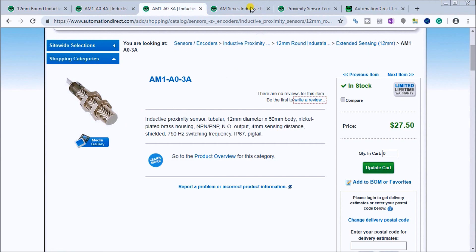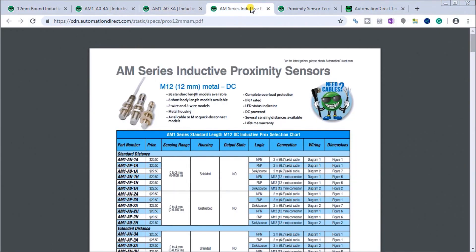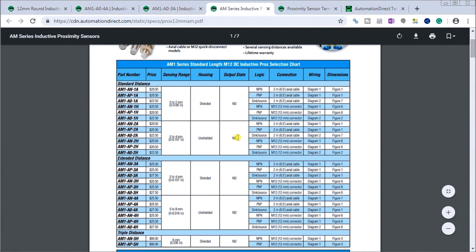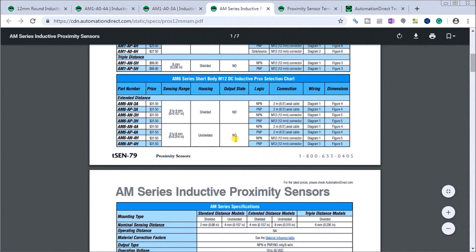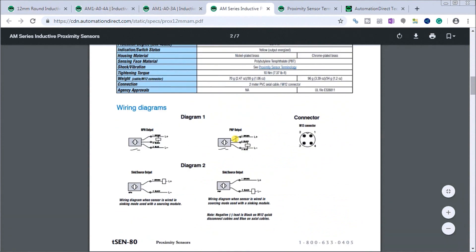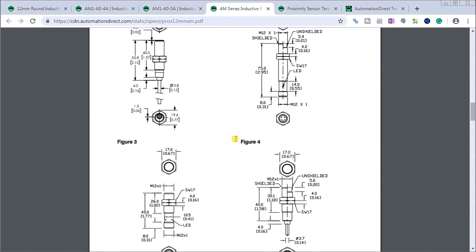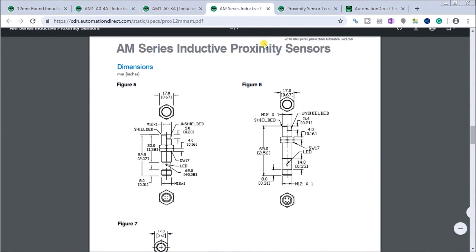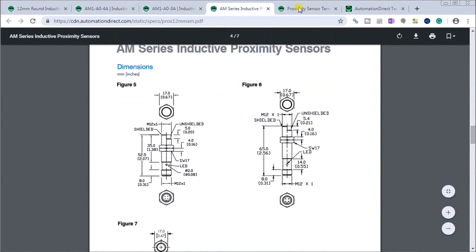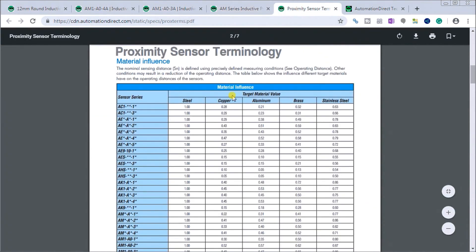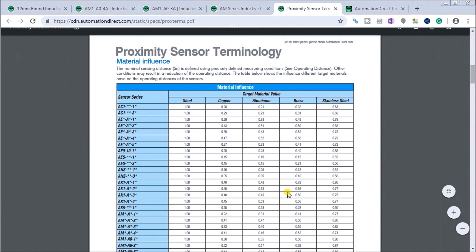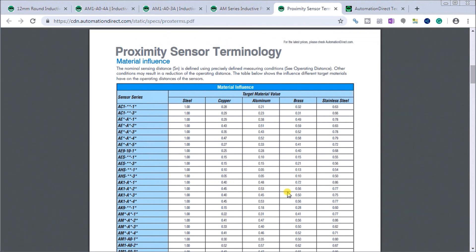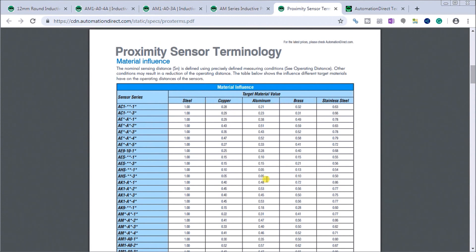Looking at the specifications, here are the specs in the charts. It gives you wiring diagrams and all the information pertaining to the proximity sensor. We have some sensor terminology and it looks at ferrous metals. This chart will give you the distances you're looking for, or the factor that you need to degrade your distance if you're looking at other materials like copper, aluminum, brass, or stainless steel.